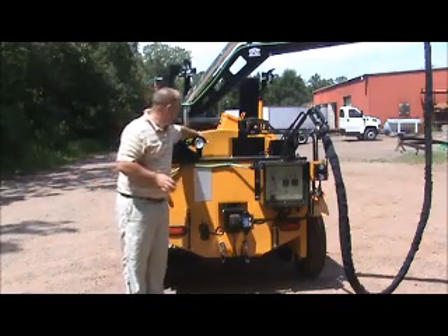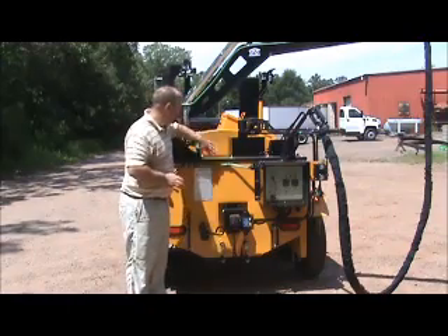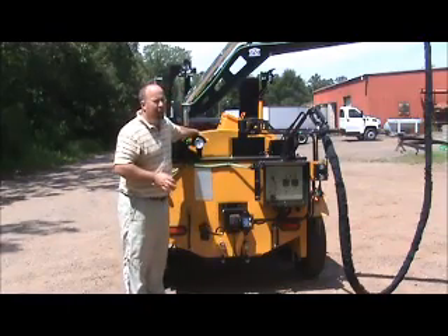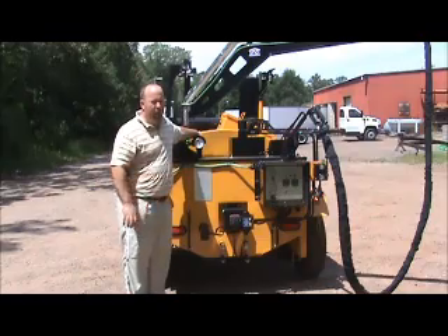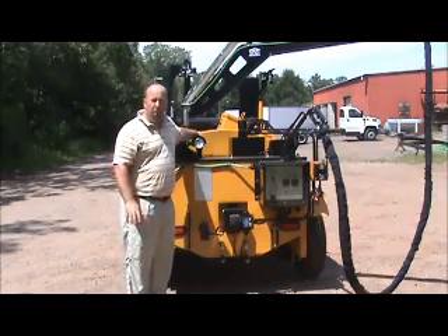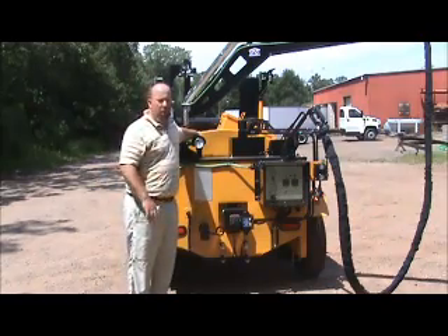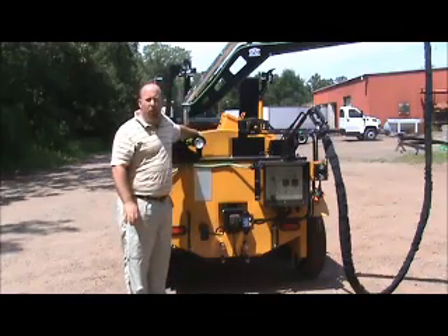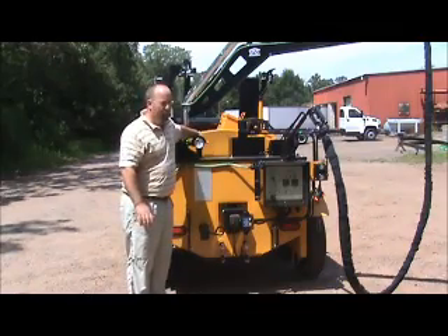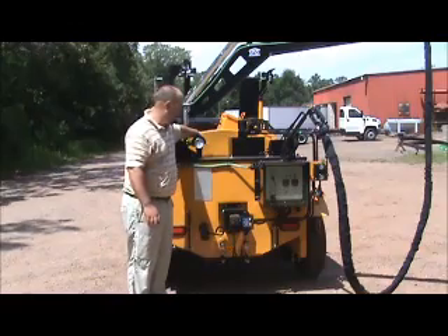If you have to torch it, be very careful, because you've got wiring. And don't ever heat on the valve. Heat on the plumbing itself. The valve is only rated to take about 600 degrees of temperature. Your hand torch is usually 1,000 plus degrees, the flame out of the end of your hand torch.